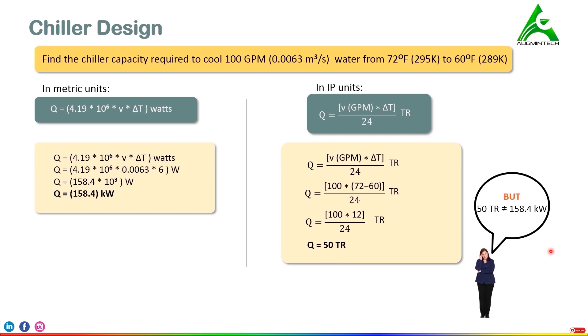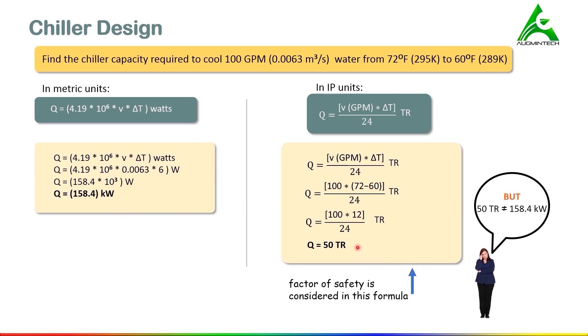There is an important point to understand: using these two different equations we get different values. Is 50 tons equal to 158.4 kilowatts? No. The reason is that in the IP formula we included a factor of safety — the value 449 was rounded up to 500 — which is why we get a different, slightly higher value. If you use the exact value of 449, the values obtained from metric and IP calculations will be the same. This is the correct explanation for the difference.